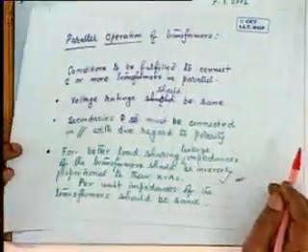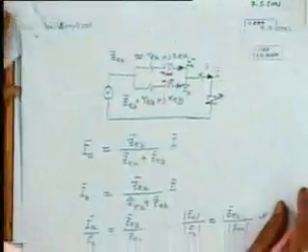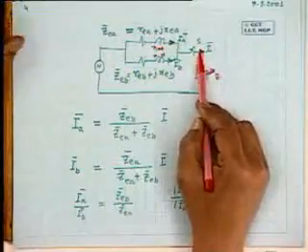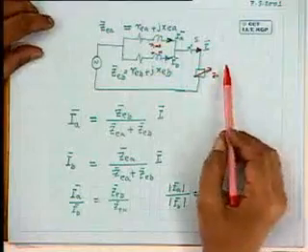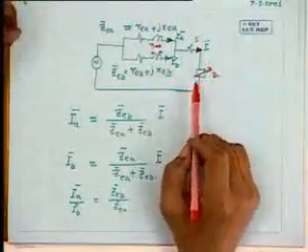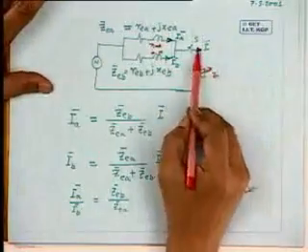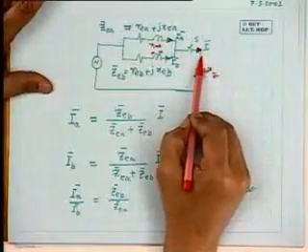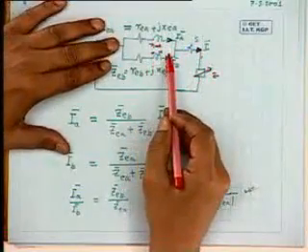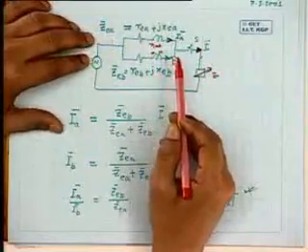So can we also apply external resistances and make the ratio proper? No, you don't have any control because these 2 transformers are in parallel. You connect an impedance. The current supplied to the load will be decided by this voltage divided by this impedance. That is fixed. But what I am trying to tell is, at any point of loading, whatever current is supplied to the load, that current will be divided in the ratio of their impedances.